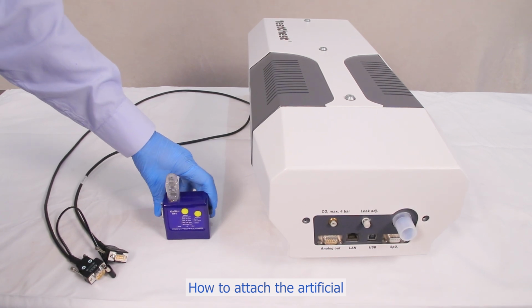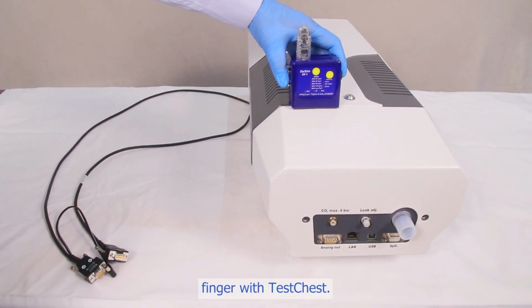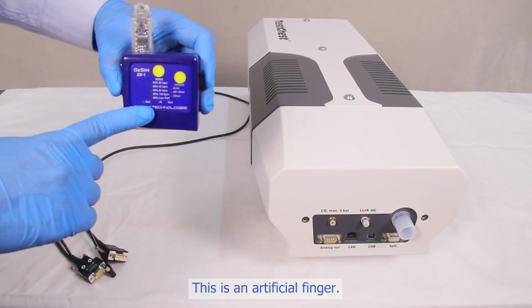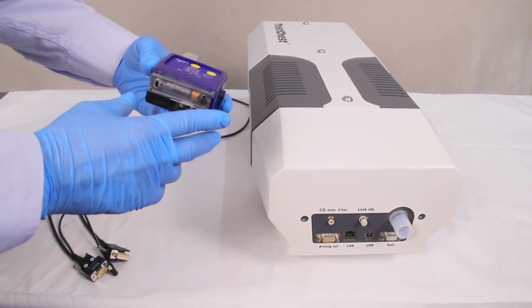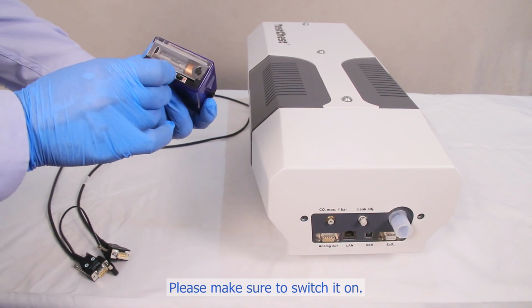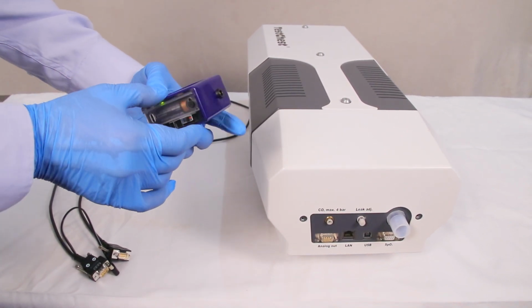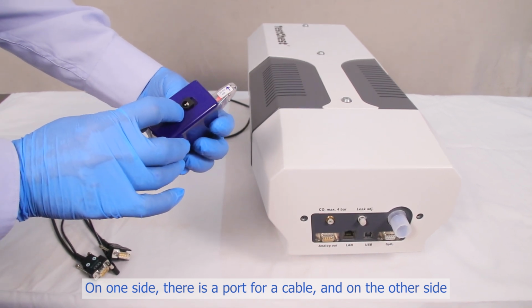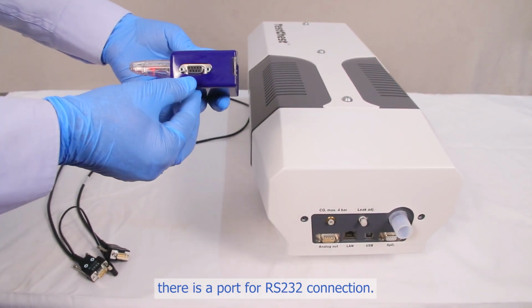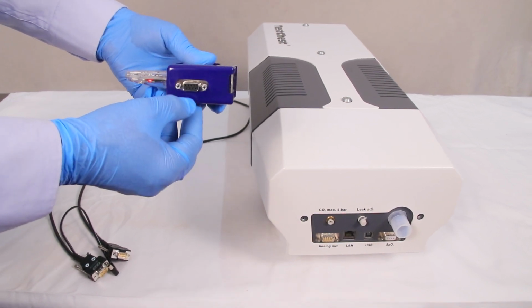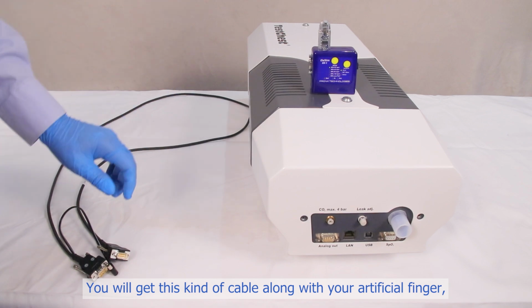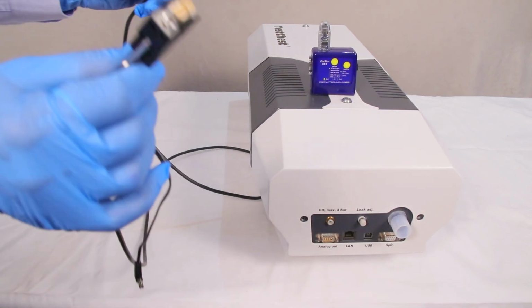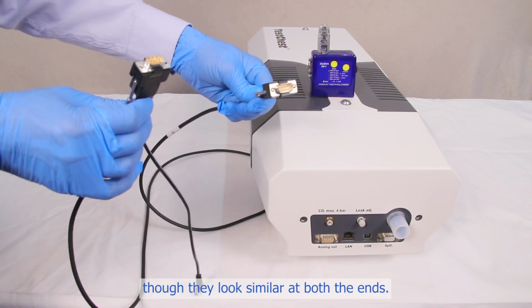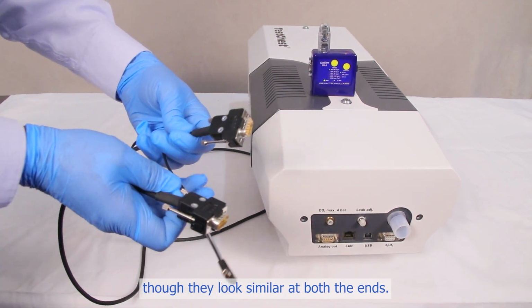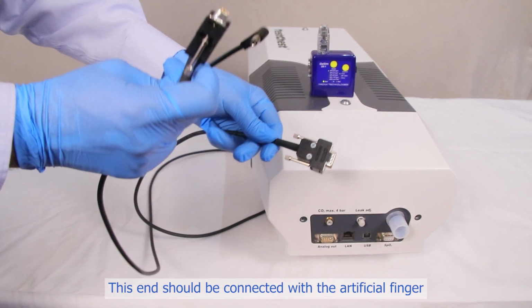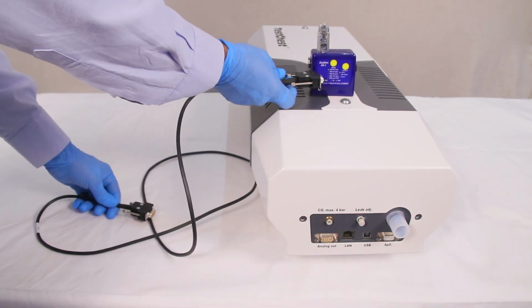How to attach the artificial finger with TestChest. This is an artificial finger. Please make sure to switch it on. On one side, there is a port for a cable, and on the other side, there is a port for RS-232 connection. You will get this kind of cable along with your artificial finger, though they look similar at both the ends. One end has an extra cord. This end should be connected with the artificial finger.